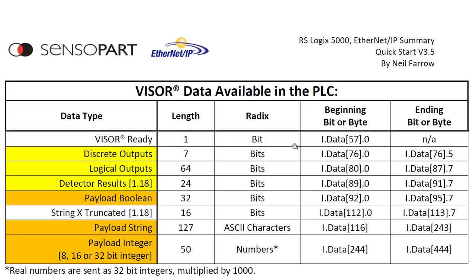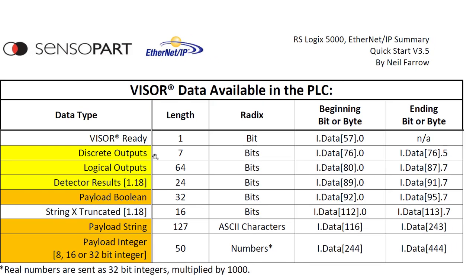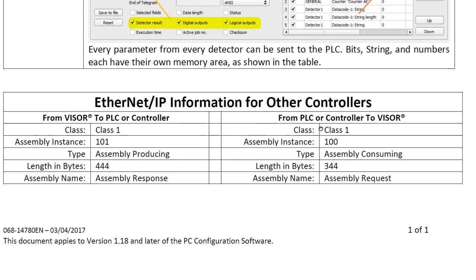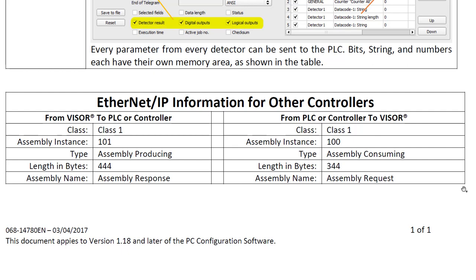This summary document shows where your data ends up in your PLC. The discrete outputs reflected here, logical outputs if you use them. Detector results are really used by almost everyone. You do have to check the box in the payload telegram tab. Payload bits start at 92, payload strings start at 116, and payload integers start at 244. So down here, if you don't have a Rockwell PLC, this is all the information you should need to configure Ethernet IP for your controller.